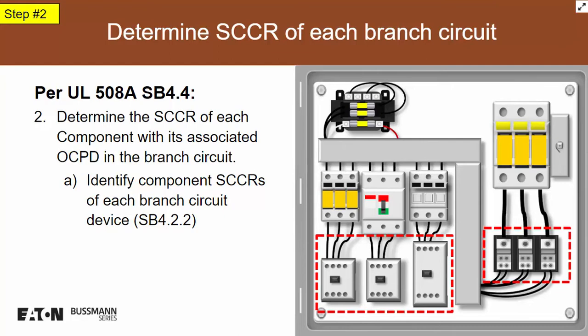Then on the panel itself, we'll also have 3 squares down at the bottom and 1 big square. One's a drive on the right, and the other 2 are basically contactors, and they're protected by their associated overcurrent protective device. In general, contactors and drives, 50 horsepower and less, have a standard SCCR rating of 5 kA. But with the associated fuse or associated breaker, it can jump up to 65,000 or 100,000 amps. So we want to make sure step number 2 is looking at the combination ratings, and that will be our answer for step number 2. Basically, we cannot exceed step number 1 because that's our overcurrent protective device and we can't change that.